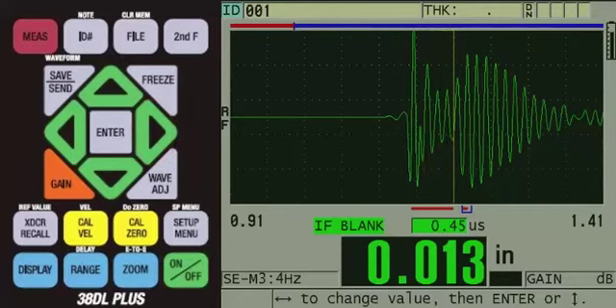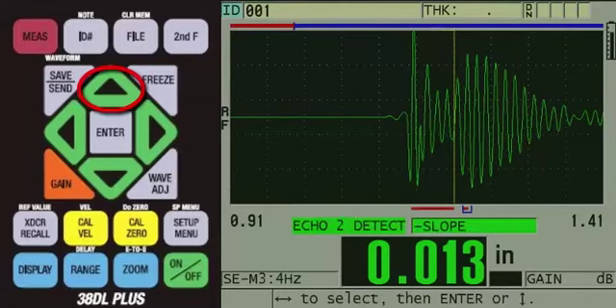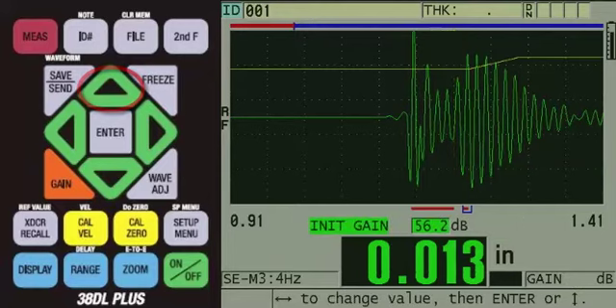To ensure these measurements are easily captured, we will increase the initial gain slightly. To do this, press the up arrow to INIT gain. Then we will press the right arrow to increase the initial gain. At this point, the user should calibrate using samples of known thickness. For best accuracy, they would calibrate using 2 samples of the same material with known thickness representing their minimum and maximum thickness. Once this is completed, we would recommend saving a custom setup.